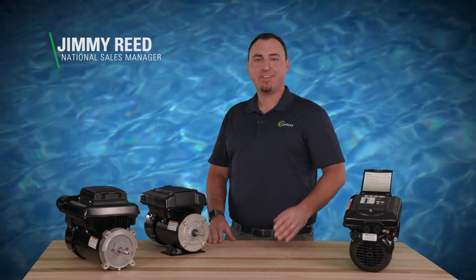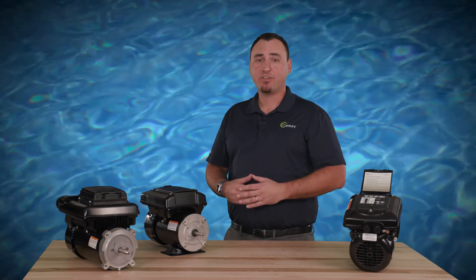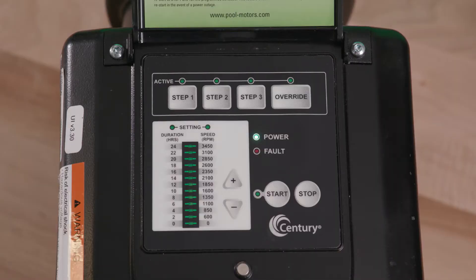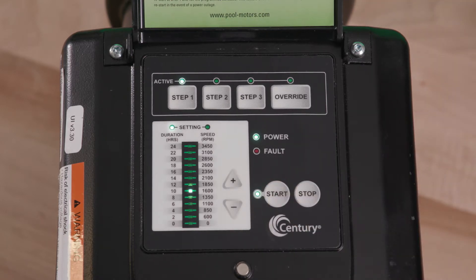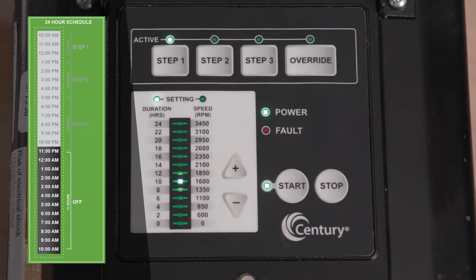Jimmy Reed here with Regal. The V-Green motor is designed to restart automatically every 24 hours. Let's discuss how to run the program's schedule using the integrated timer and keypad. The 24-hour countdown begins when the Start button is pressed. The motor will run through the customized schedule and restart at Step 1 every 24 hours. To initiate operation of the program schedule, apply power to the V-Green motor and press the Start button. Take note of the time, as this will be the daily start time for the program schedule. For example, if the Start button is pressed at 10 a.m., the V-Green motor schedule will restart at Step 1 every 24 hours at 10 a.m.